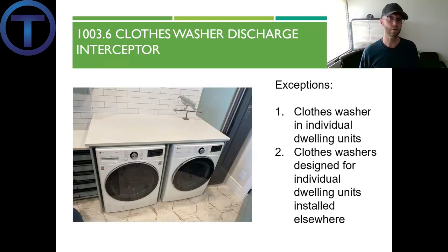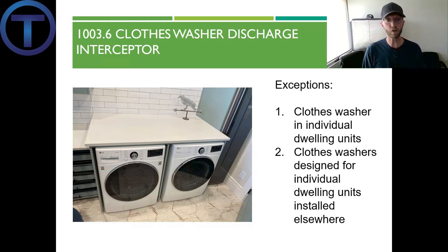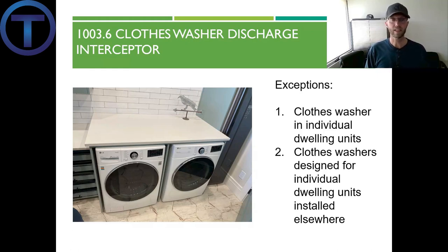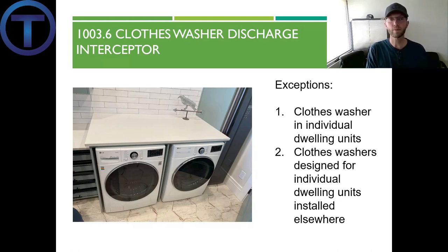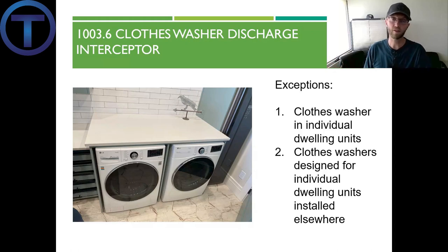There are some exceptions to that rule. Similar to not needing a grease separator for your kitchen sink, they do not require an interceptor for a private or individual clothes washing machine — that's the first exception. The second exception states that if it's a clothes washer intended for individual dwelling use — basically a typical washing machine — but installed in a different setting that's not an individual dwelling, it's still the same appliance, so they're not as concerned about that.